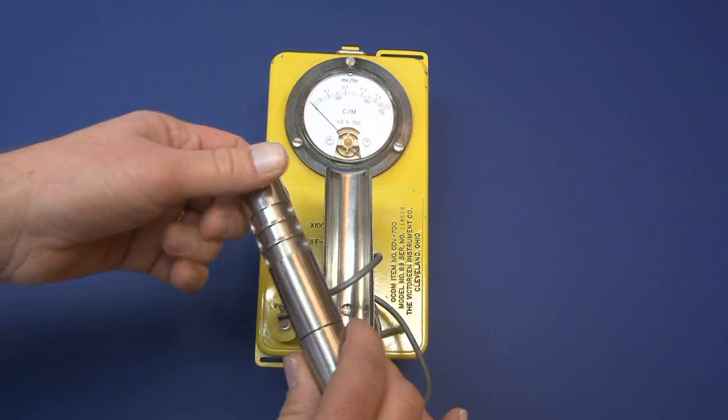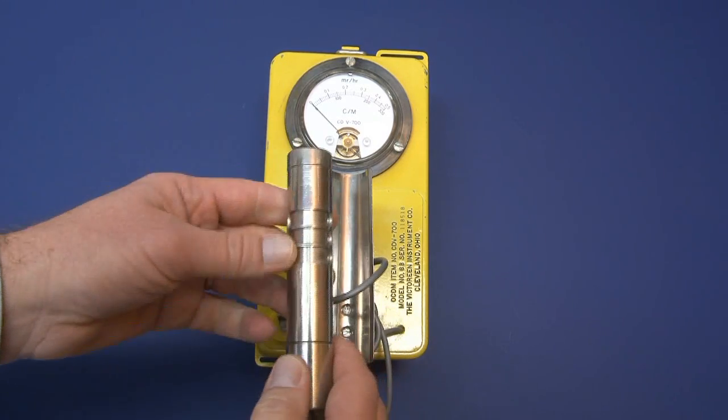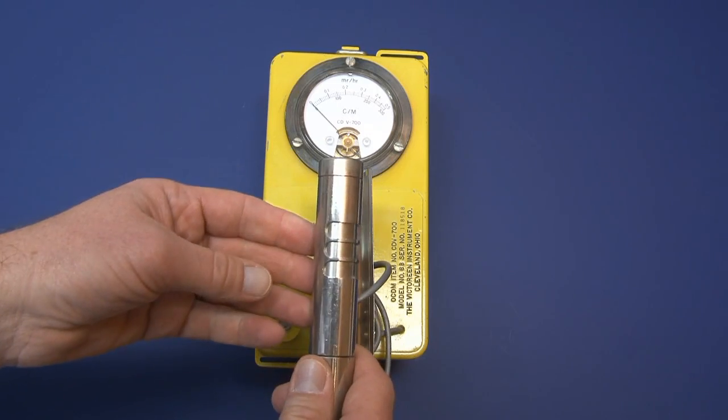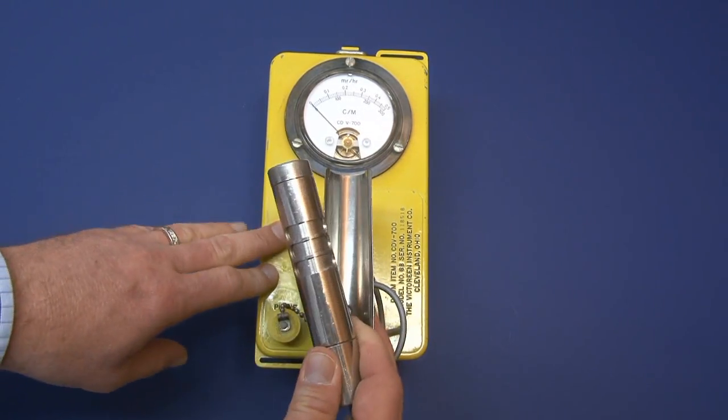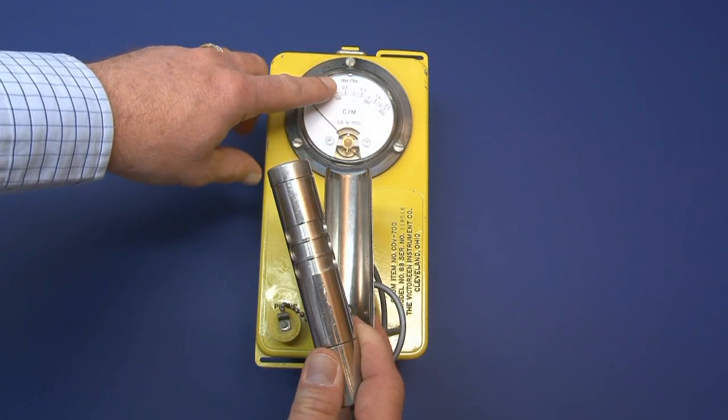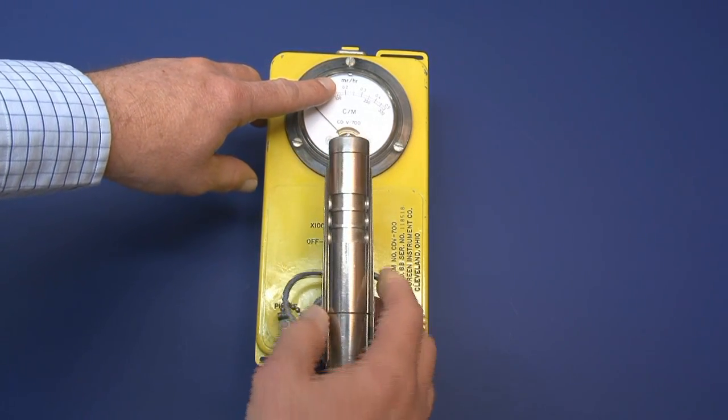The idea when they designed this instrument was that with the window closed, you would detect gamma radiation only, and you'd be taking radiation exposure rate measurements, and you would report your readings in mR per hour.